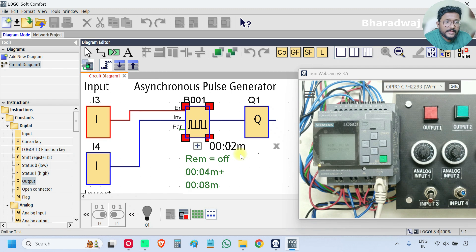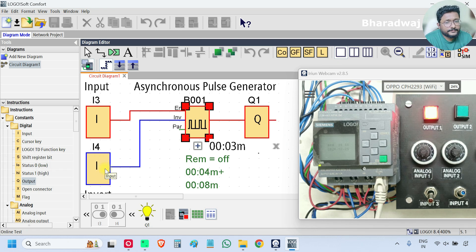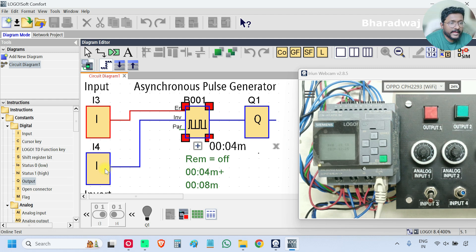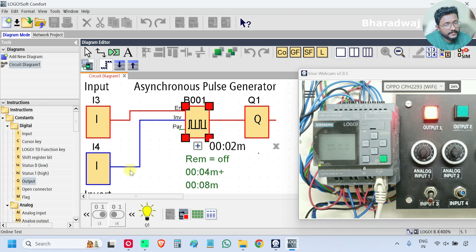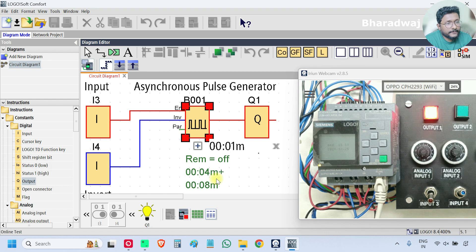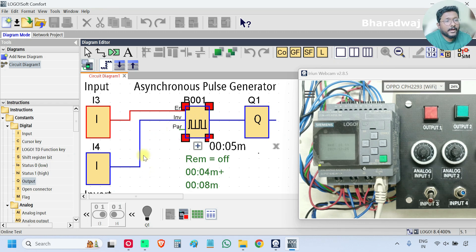There is one more input which is INV — Invert. What it will do is simply invert the on-time and off-time values. Whenever this Invert is on, the 4 seconds and 8 seconds will be exchanged. On-time will be 8 seconds and off-time will be 4 seconds — the name itself says it will invert the on-time and off-time.